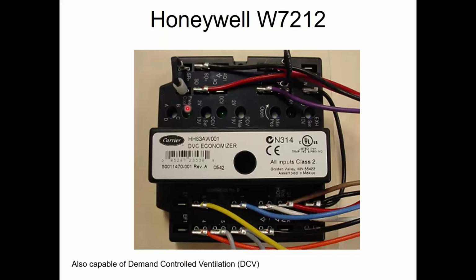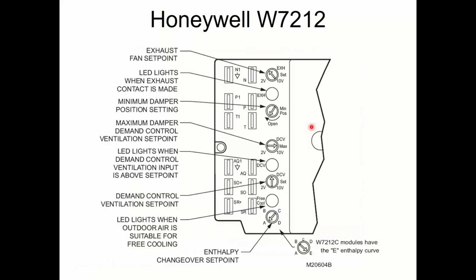If you have this guy, the 7200 series from Honeywell, this one says Carrier on it because they private brand it for lots of manufacturers, but almost all of them are made by Honeywell. There's 1, 2, 3, 4, 5 settings on it. So I still have that enthalpy switch on there if you have an enthalpy sensor. I have the minimum damper position switch. And then I have some switches for demand control ventilation with CO2, both a set point and a maximum throttle.